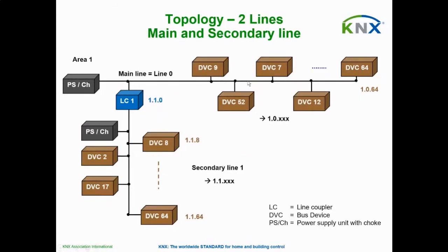Pretty often, we just have two lines set up with a main line and a secondary line. Simple to use, easy to use. Many, many smaller projects use this topology. All you need to remember is you need one line coupler, two power supplies, and then your devices just sit on the appropriate line, however you number them.